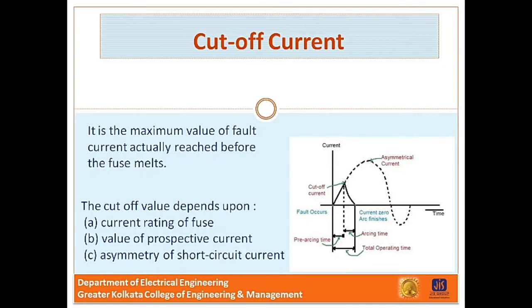The outstanding feature of fuse action is the breaking of the circuit before the fault current reaches its first peak. This gives the fuse a great advantage over the circuit breaker, since the most severe thermal and electromagnetic effects of short circuit currents are not experienced with a fuse. The circuits protected by a fuse can be designed to withstand a maximum current equal to the cut-off value. This consideration, together with the relative cheapness of fuse, allows much saving in cost.